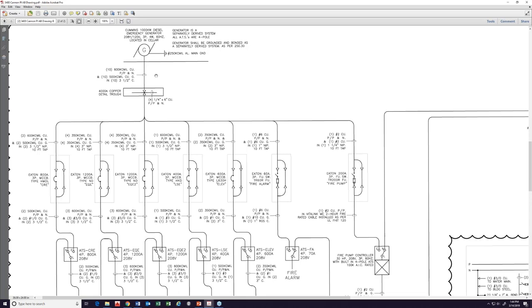And that is actually in the code in 445, I don't remember the exact subsection, maybe .14, something like that, that the output conductors of the generator, which the code calls the generator conductors, have to be sized 115% of the full load output of the generator. And that's how they have enough protection. And they're adequately sized.